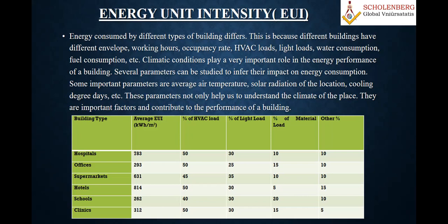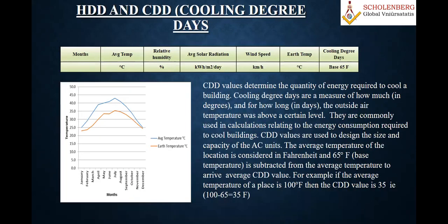These are some of the average energy intensities for various kinds of buildings: hospitals, offices, supermarkets, hotels, schools, and small clinics. Also, when you do the calculation or the energy efficiency design, you may consider what we call cooling degree days as well as heating degree days, CDD and HDD. Here I'm talking about the CDD in Muscat. But mostly when you do it in Europe or elsewhere, you can take this data from the meteorological design values. This must be in the standard also.